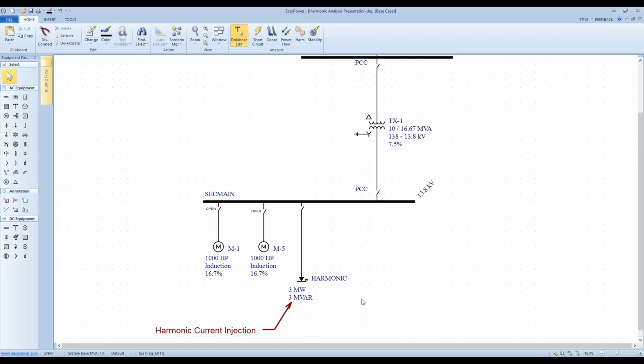But again, if somebody's taking measurements, you can put that on the bus as a single point current injection, and not bother modeling all these other devices within the system. So it depends on how you're receiving the data. It's quite a bit of work to go through a facility and model each individual load in a facility.